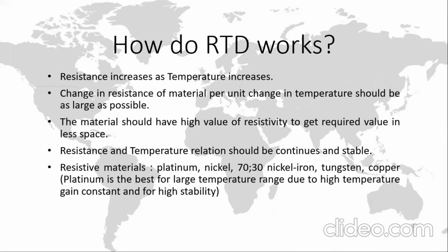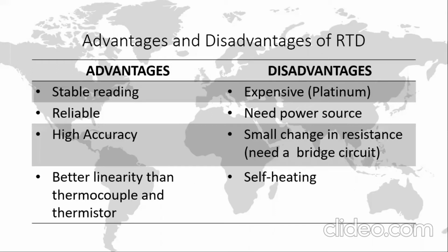So the material should have a high value of resistivity to get the required value in less space. Resistance and temperature relations should be continuous and stable. Examples of resistive materials are platinum, nickel, tungsten, copper, but platinum is the best for large temperature range. It is due to high temperature coefficient, constant gain and high stability.